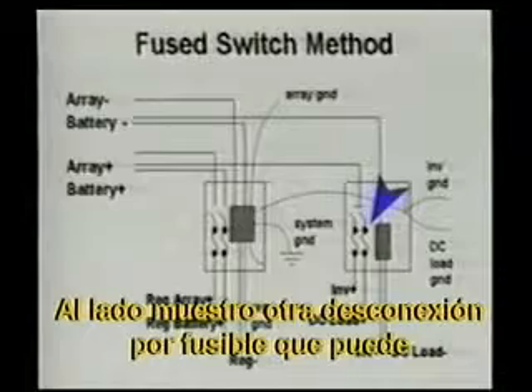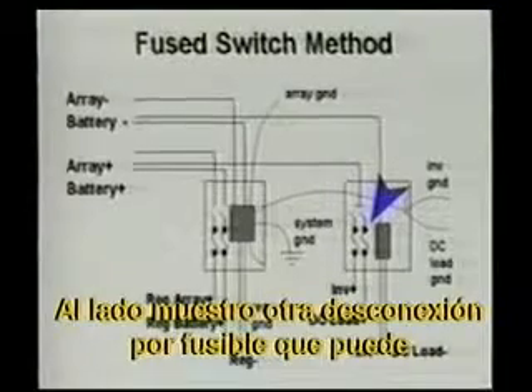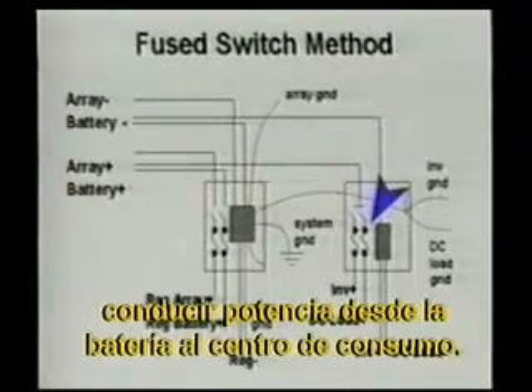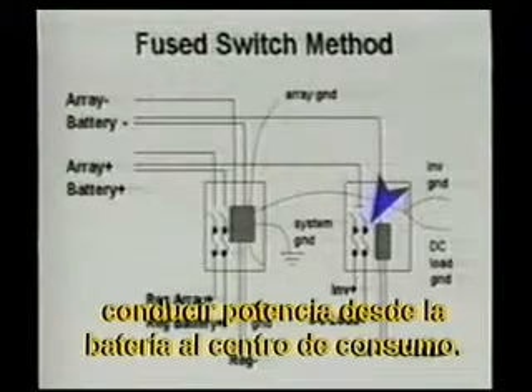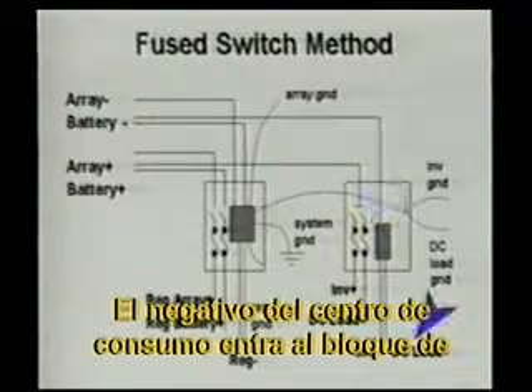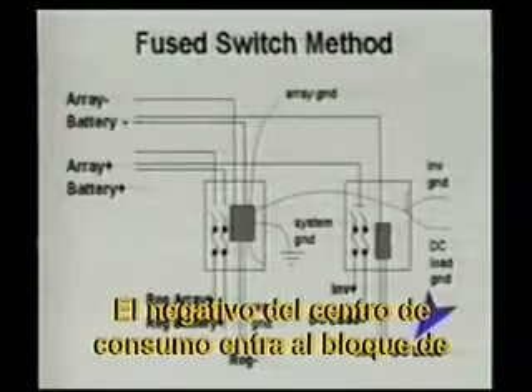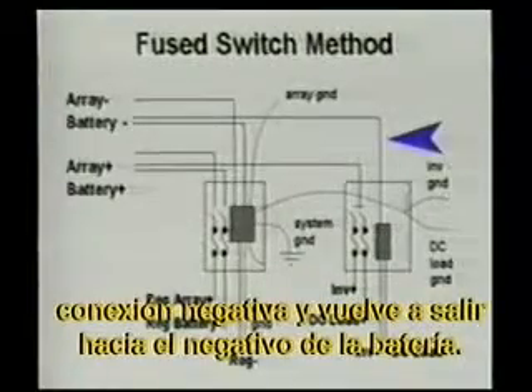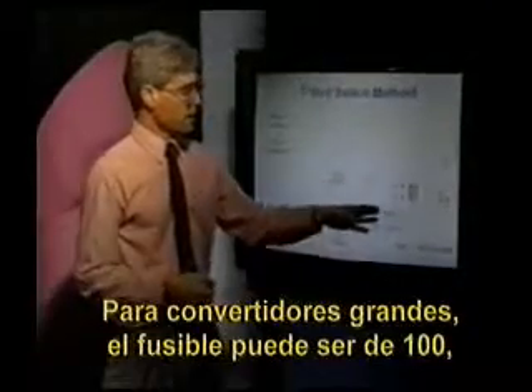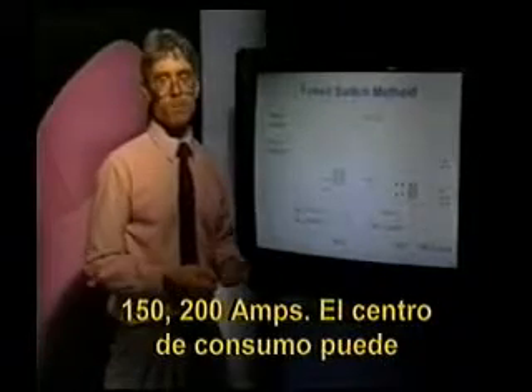Next to that, I show another fused disconnect that can carry power from my battery to my load center. And the negative from my load center would come into the negative wiring block and flow back out to my battery negative. Again, if I'm choosing large inverters, the inverter fuse might be 100, 150, 200 amp fuse. My load center might involve a 100 amp fuse.